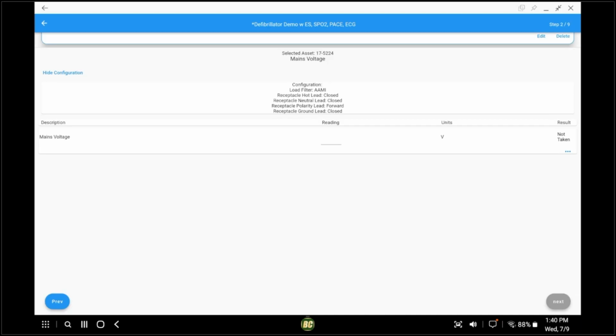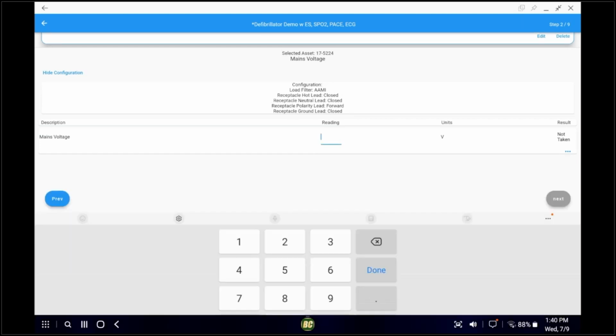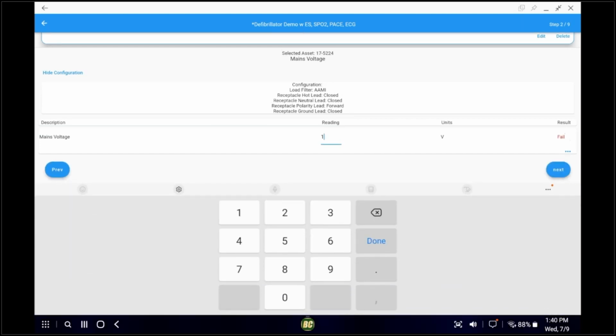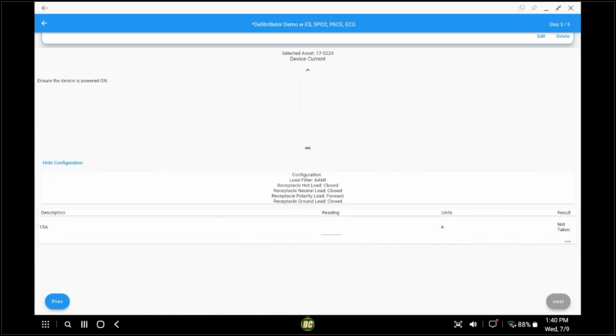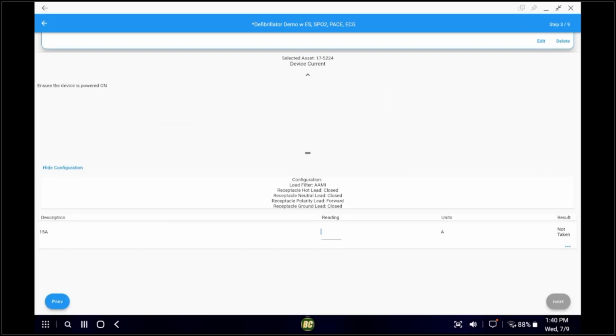Over here it's asking for mains voltage. Let's say you're not a BC Group customer and don't have myBC test equipment. This is an excellent spot for you to use your own meter, like a Fluke or a Datrend. You can type in your voltage, 120 volts, and it gives me a pass or fail condition. Same thing with equipment current.